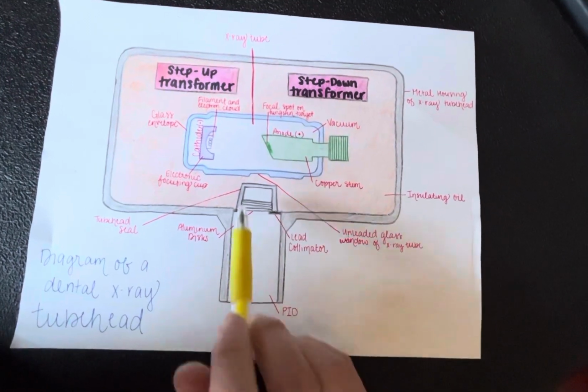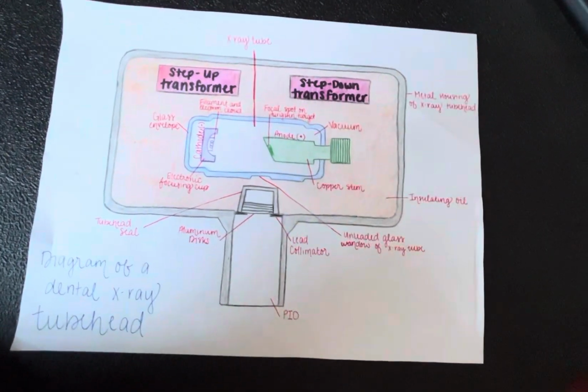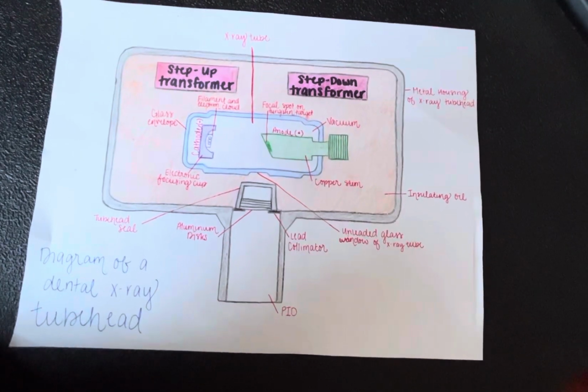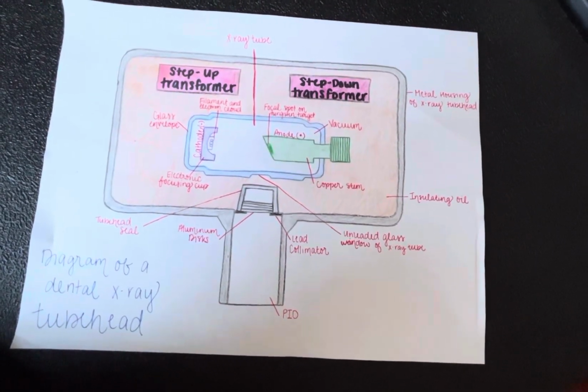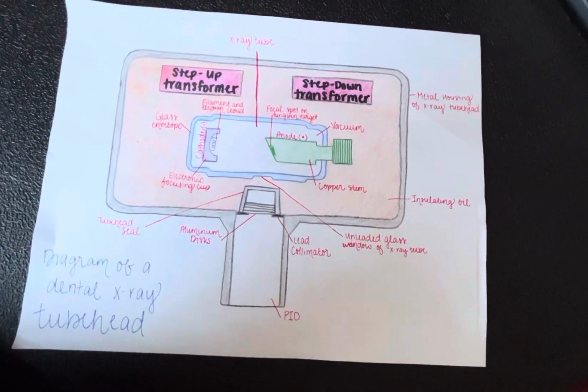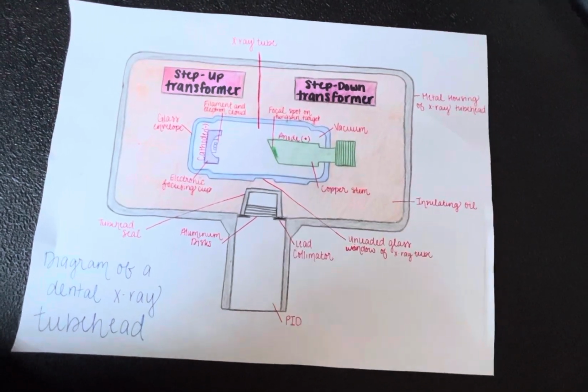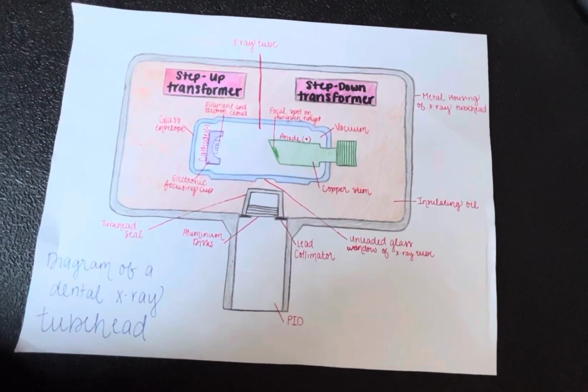Next, we have the tube head seal. It's an aluminum or lead glass covering of the tube head, and it allows X-rays to exit the tube head. It keeps the oil in and also acts as a filter to the X-ray beam.